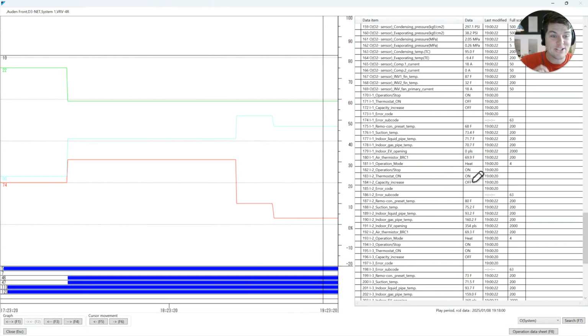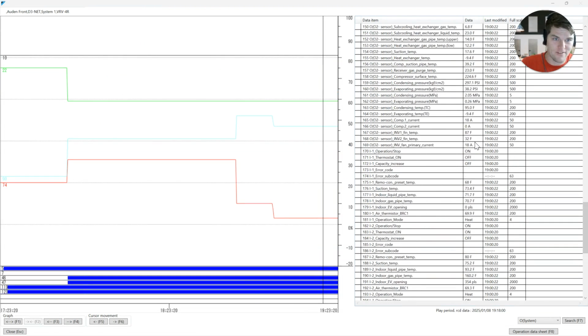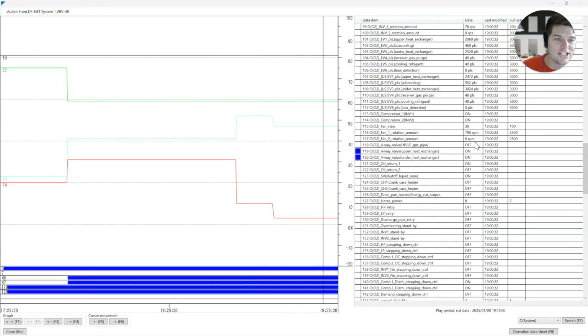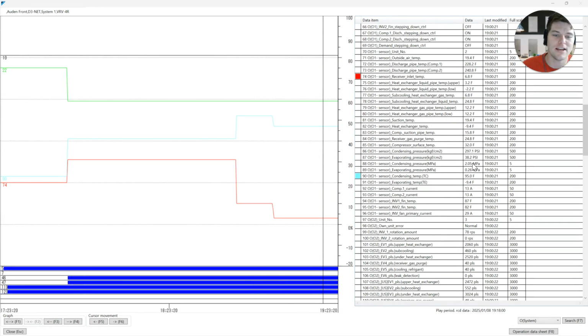Let's look at it. So 95 degrees, we know this is 95 degrees. What is my saturation temperature, right? This is all about saturation temperature. It's 95. Oh no, I have 0 degrees subcooling at my indoor fan coils. Is that good or bad? That is bad. What happens if I had 1 degree subcooling, which I think I had on one of those indoor units? All right, I'll give you one. 1 degree subcooling on my indoor unit.